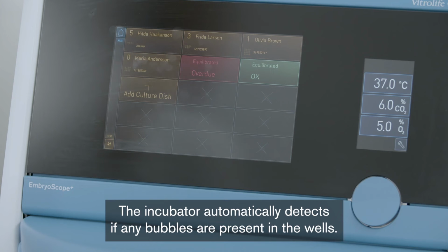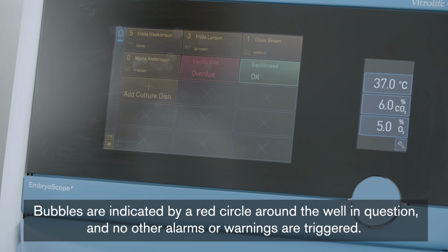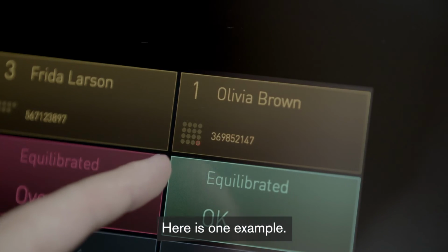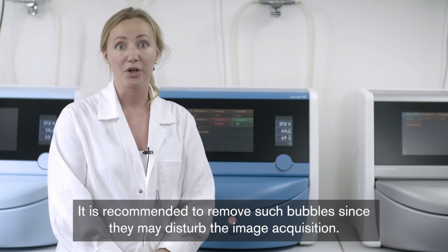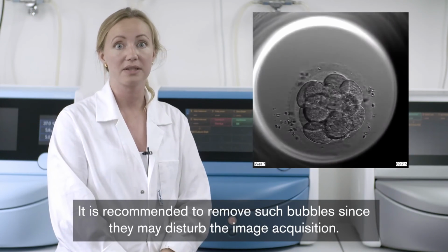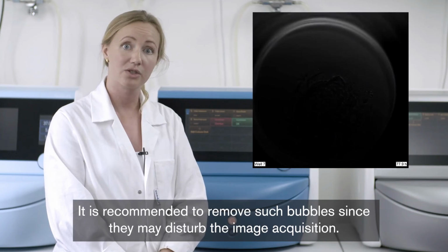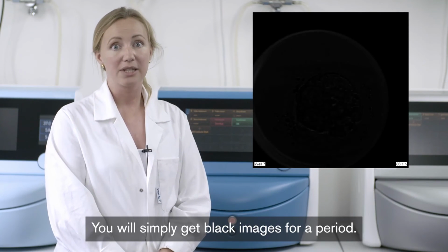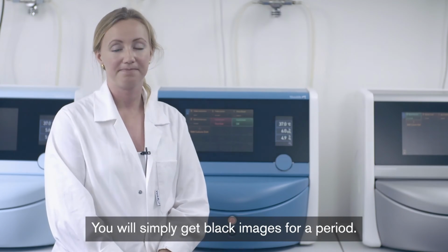The incubator automatically detects if any bubbles are present in the wells. Bubbles are indicated by a red circle around the well in question, and no other alarms or warnings are triggered. Here is one example. It is recommended to remove such bubbles since they may disturb the image acquisition. You will simply get black images for a period.